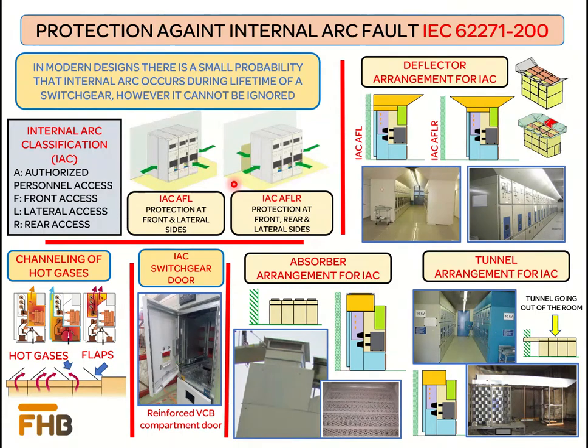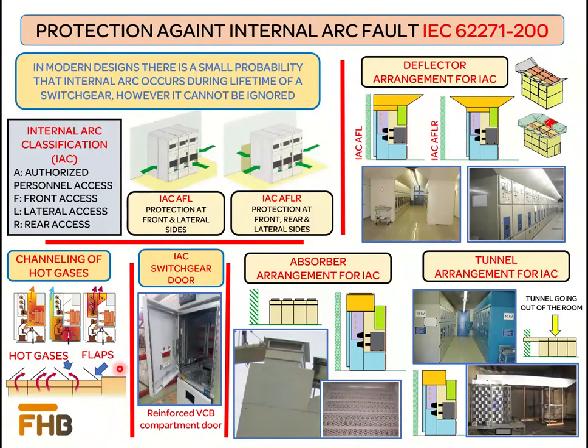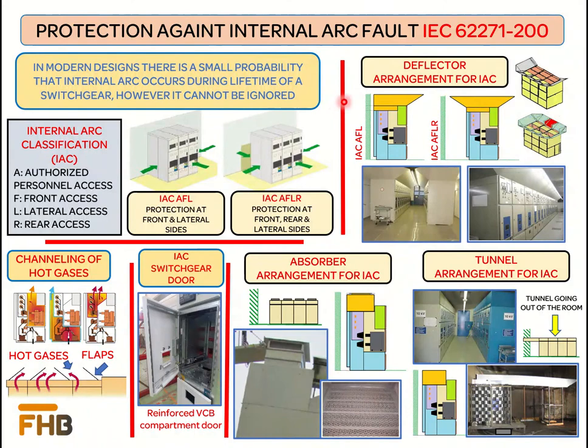The arc ducts provided within the switchgear play an important role in reducing the pressure within the enclosure in case of an arc fault. These ducts direct hot gases to the upper side of the switchgear, where gases are exhausted by the opening of flaps on the switchgear roof. These ducts are made in all three compartments of the switchgear containing power components: the cable compartment, the circuit breaker compartment, and the busbar compartment. In addition to the ducts inside the switchgear, there are three different arrangements to further safely channel the hot gases coming out of the switchgear.